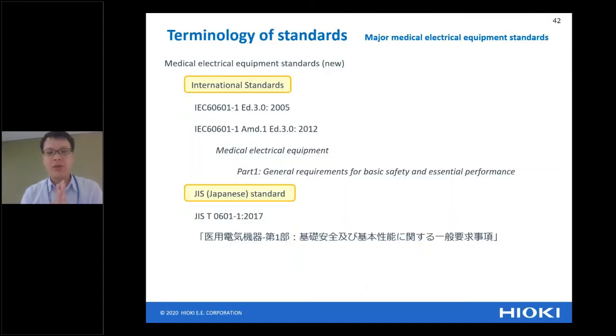Next, I want to talk about the major medical electrical equipment standards, the latest versions. For the international standard, IEC 60601-1 edition 3, from 2005, and also amendment 1 edition 3.1, 2012. This is the latest for medical electrical equipment. Also for reference, the JIS Japanese standard is available: JIS T 0601-1, 2017.